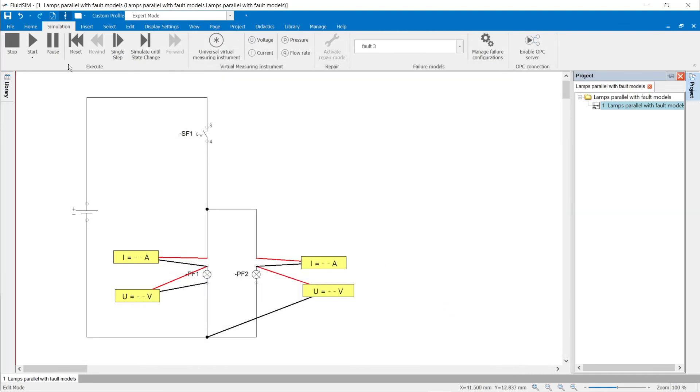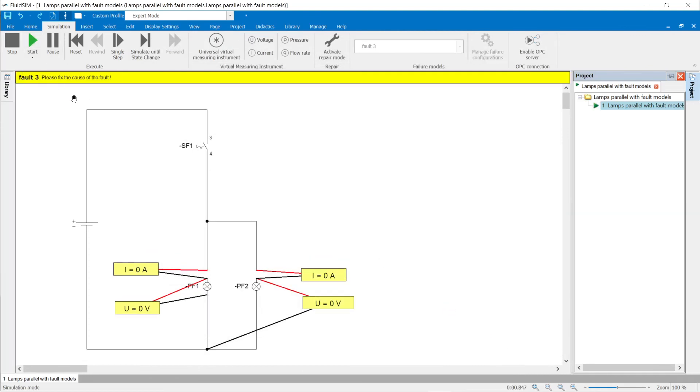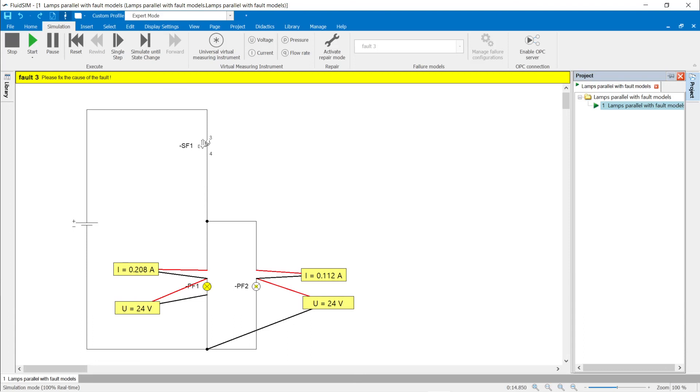The operating voltage of 24 volts is therefore divided between the internal resistance of the lamp and the cable. The current through the current path also decreases due to the summation of the resistances in the cable and lamp. The lamp lights up weakly or not at all. Errors that can be parameterized are very practical, since errors often occur slowly during operation due to wear, corrosion, or other causes.